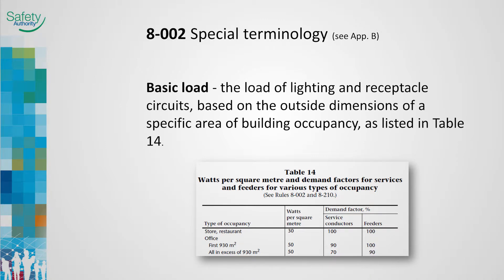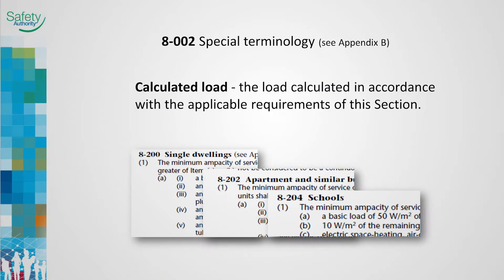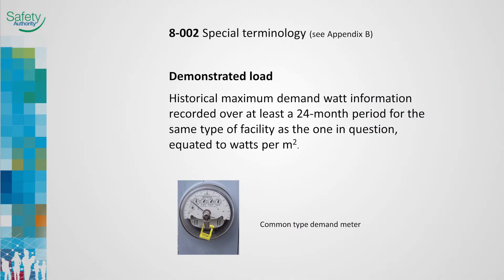Rule 8-002, Special Terminology, introduces three common terms and provides definitions, with further information provided in the Appendix B notes. The basic load may be considered to be the minimum typical lighting and receptacle load found within a building based on its outside dimensions and the type of occupancy. The basic load does not include equipment such as special lighting or other power and electric space heating loads. The calculated load is defined as the load determined using the relevant rules of Section 8. These load and demand factors are based on generally accepted assumptions and engineering analysis as well as load data and experience obtained from similar occupancies. The demonstrated load is defined as the load obtained from one type of occupancy over a relatively long period of time that can be used to determine the load requirements for occupancies of a similar type and style.